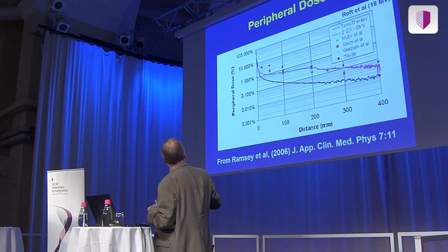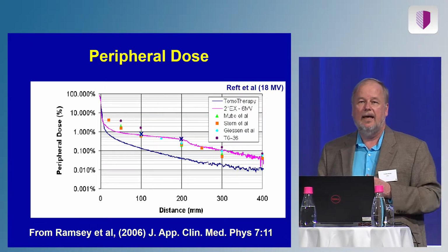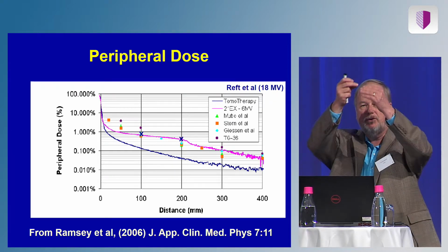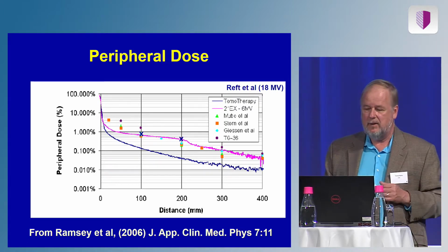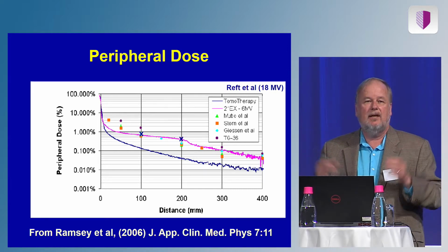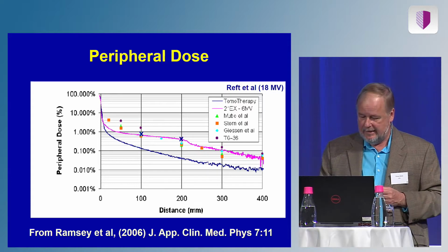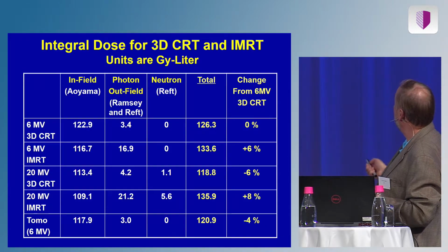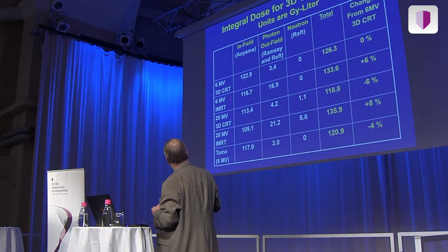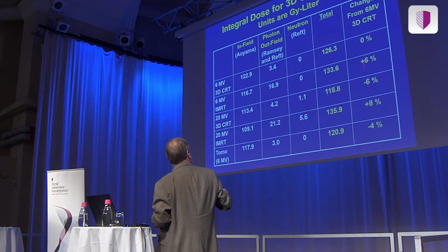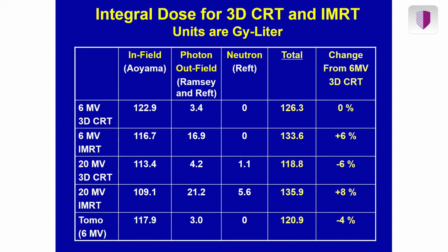This is a log linear graph, and so it's about a factor of 10 reduction if you put in much thicker primary collimators. And so, on the tomotherapy machine, there was 23 centimeters of tungsten in the forward direction. And of course, it had to be thick in the forward direction because bremsstrahlung comes out the forward direction, and it was much thinner at the back. But adding this, it's a bit costly, $10,000 or so for that much tungsten machined, makes a big difference. So if we then go and look at this comparison, 6 MV 3D conformal versus IMRT, 20 MV 3D conformal versus IMRT, then you can see, if we just look at the 6 MV as compared to 20 MV 3D conformal, that's why people use 20 MV for conventional 3D CRT, because you could get a 6% reduction in the integral dose.